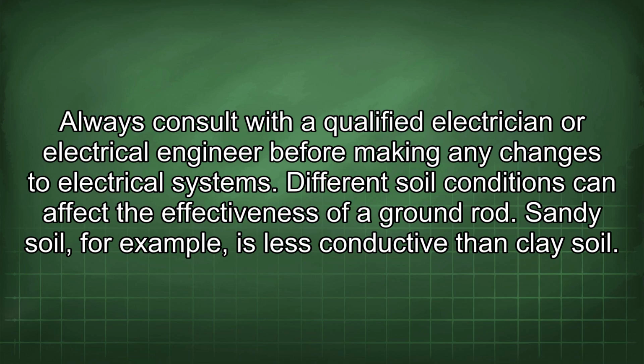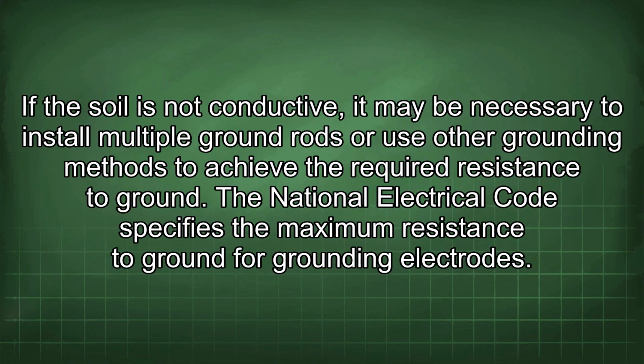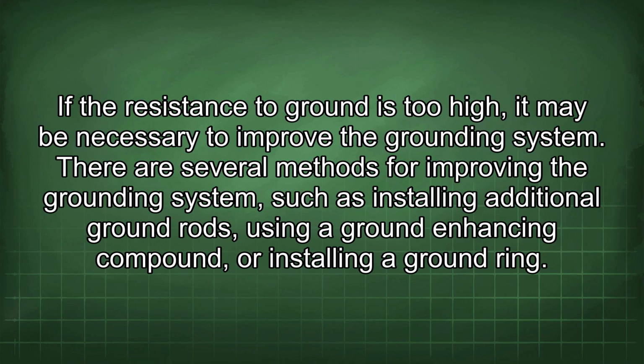Different soil conditions can affect the effectiveness of a ground rod. Sandy soil, for example, is less conductive than clay soil. If the soil is not conductive, it may be necessary to install multiple ground rods or use other grounding methods to achieve the required resistance to ground. The National Electrical Code specifies the maximum resistance to ground for grounding electrodes. If the resistance to ground is too high, it may be necessary to improve the grounding system.